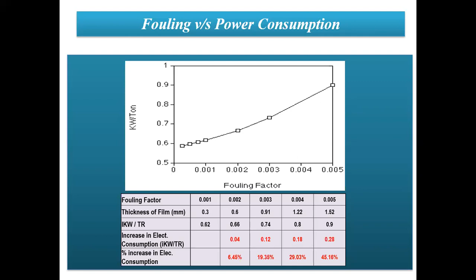In other terms, suppose in the starting days you are paying 100 rupees, now you are paying 106 rupees. So 6 rupees extra you need to pay on the electricity consumption due to the increase of the fouling factor, and thereby your approach increases and the IKW of the chiller also increases. That's why.